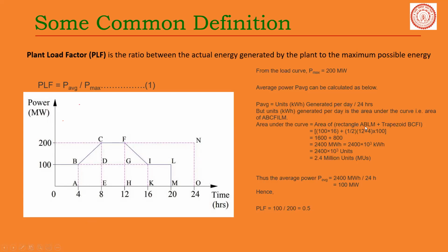So it's the area of rectangle ABLM plus the area of trapezoid BCFI, which is 100 into 16, plus half into length into breadth. Doing the calculation, it comes out to 2.4, divided by 24 hours gives megawatt, keeping units consistent at 100 megawatt. So it generated 100 megawatt on average, while it can generate up to 200 megawatt maximum. So the plant load factor is 0.5, that is PLF, P average divided by P maximum. Ideally, we aspire for PLF to be 1.